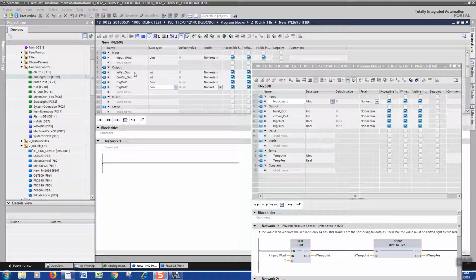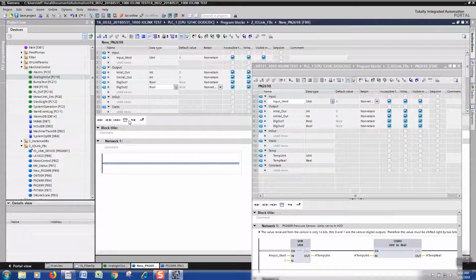All right. So you got your inputs and outputs ready to go. Now, you've got total bit length is 16, but you're only using 14 bits of it. Because the first two are not relevant for right now, and these two are those outputs. All right, so you got to take this information and shift it so that you get the proper value out. So put in a shift register from your tools there. I select it out of there.